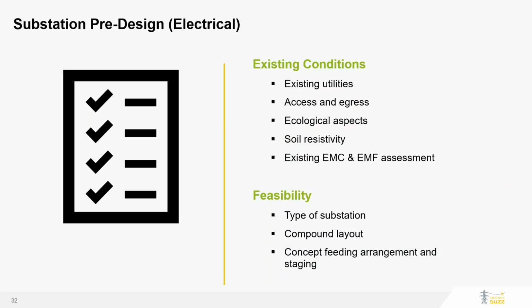When looking at feasibility of a possible new sub, we need to consider the type of substation and the compound layout. A 400 kV substation, for example, will have a larger footprint than that of a 132 to 33 kV sub. Likewise, internal switchgear occupies a smaller footprint than that of external equipment. Feeding arrangements and staging also require early consideration to ensure that supply is maintained during the construction stage.